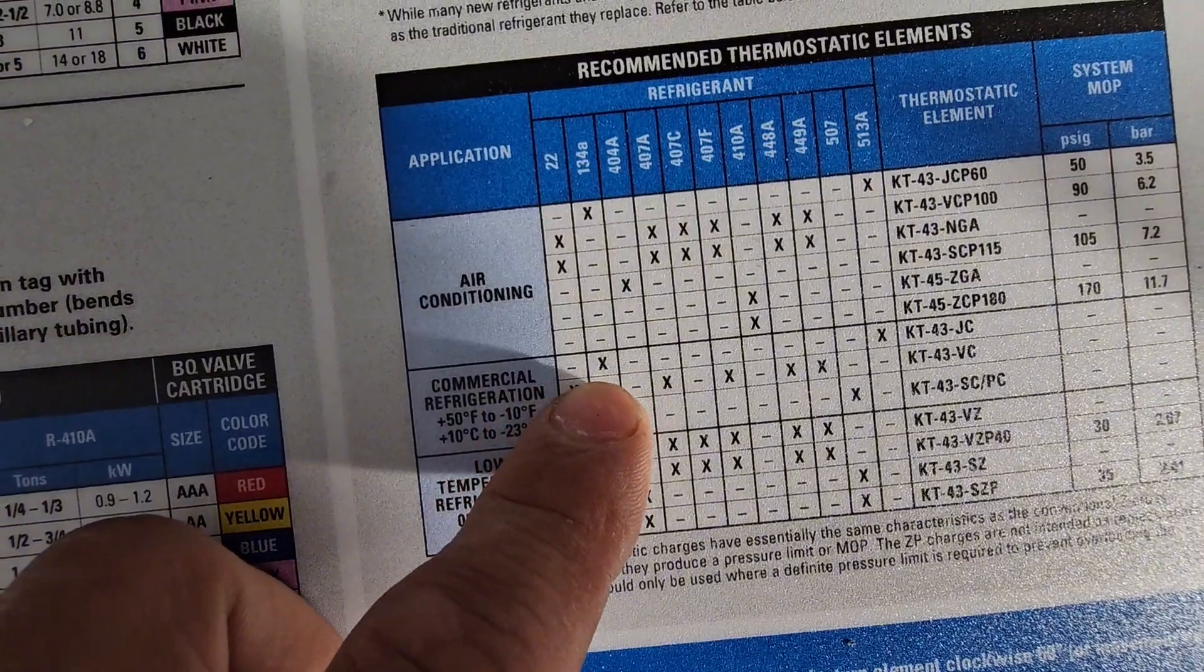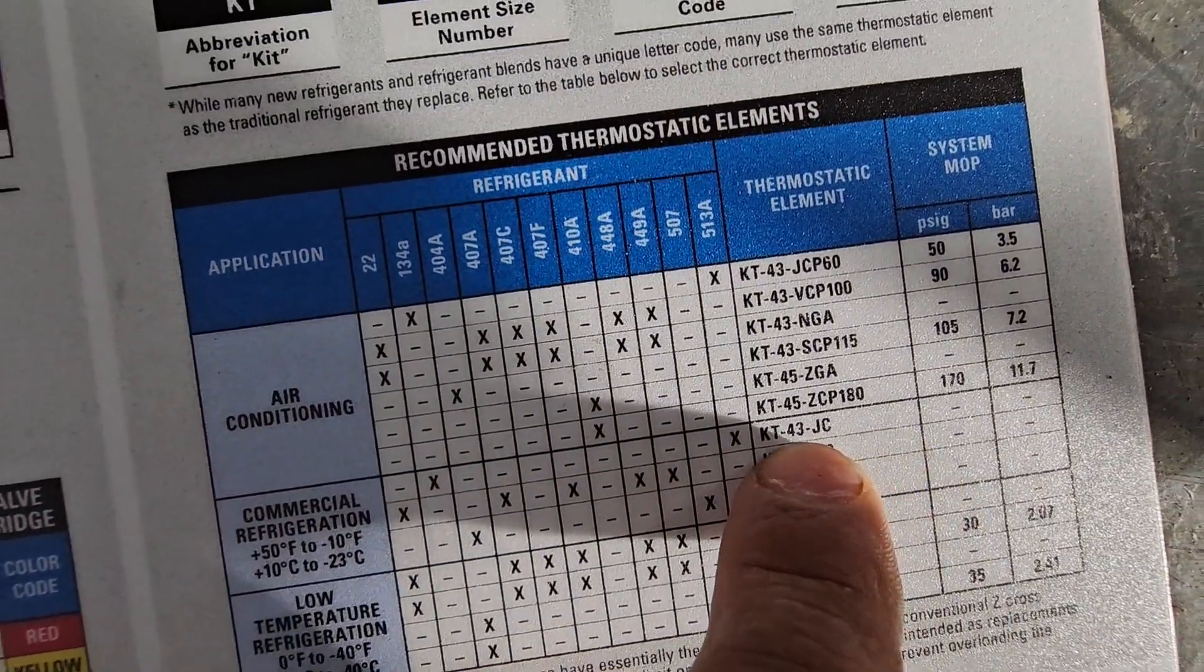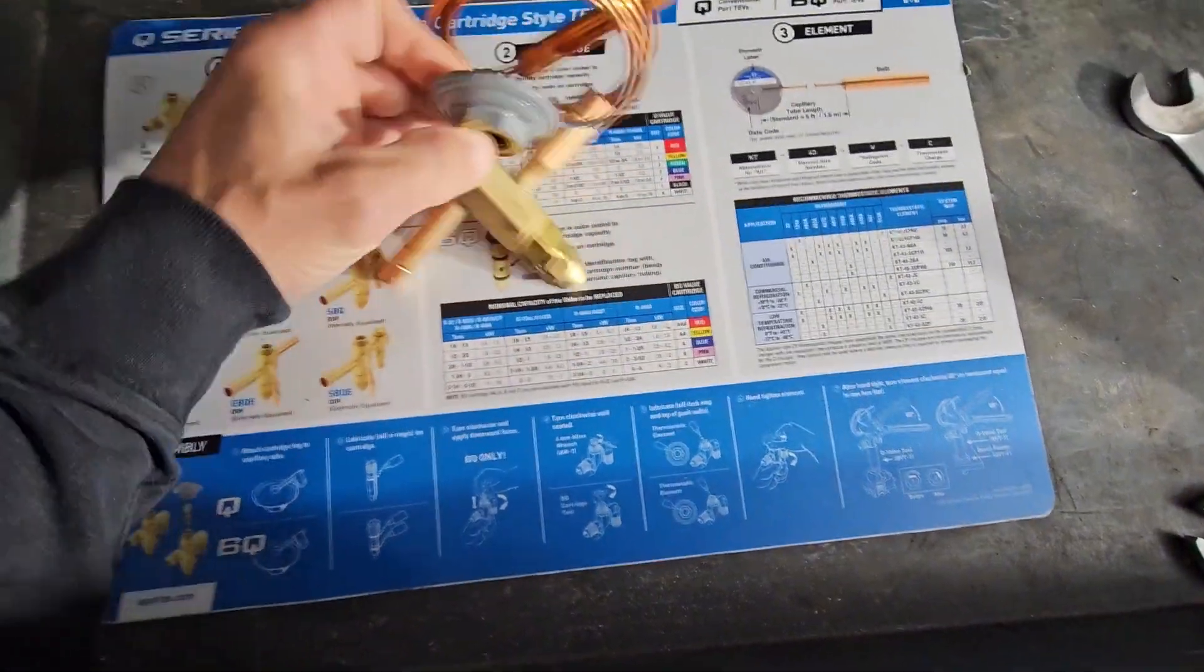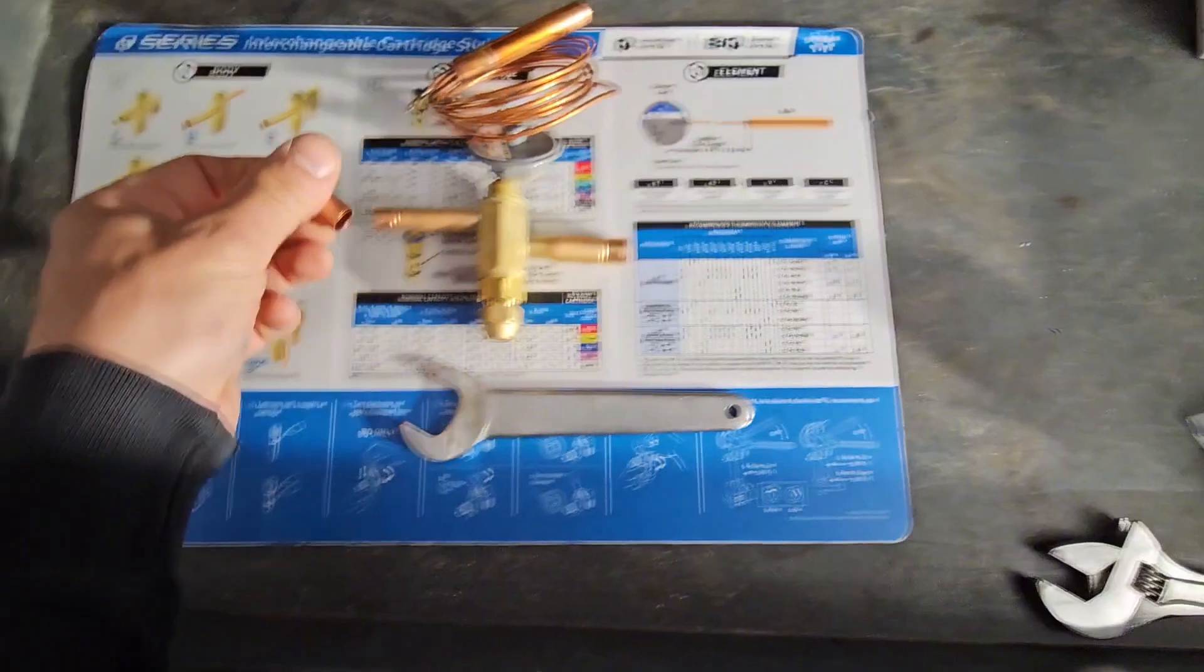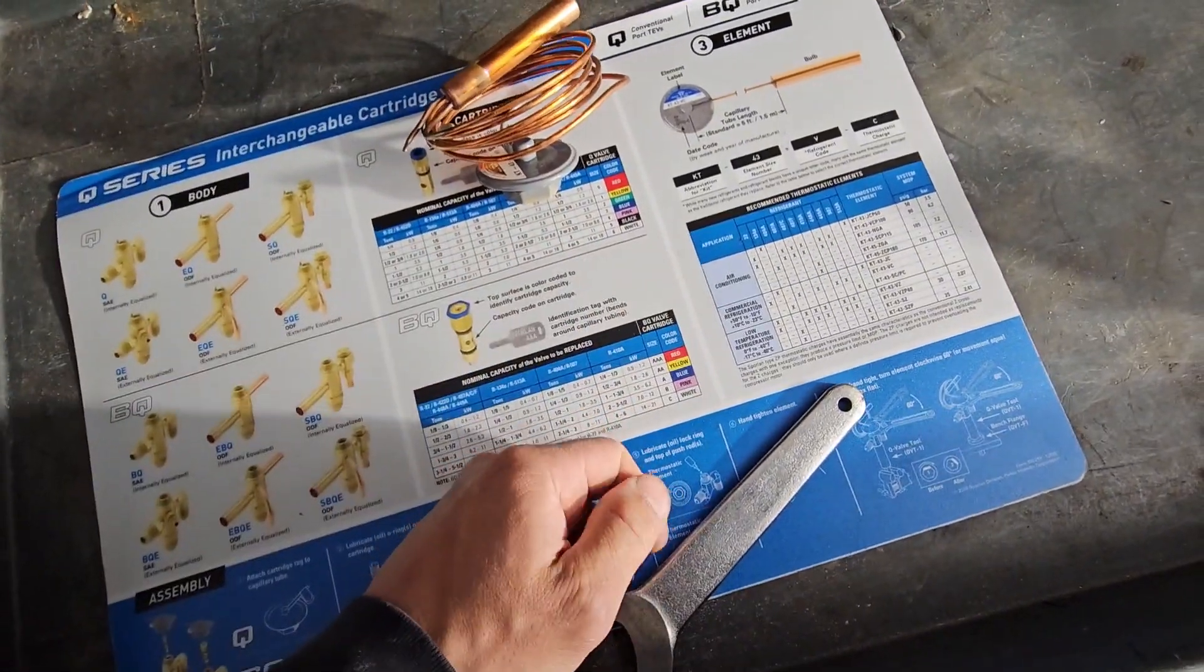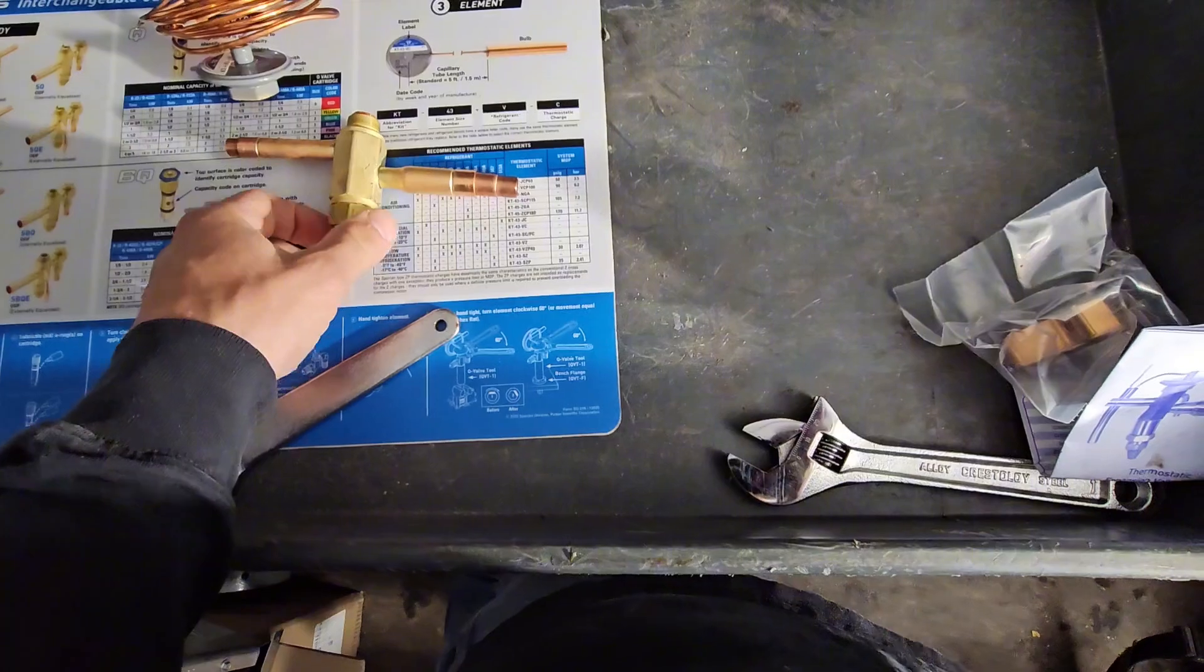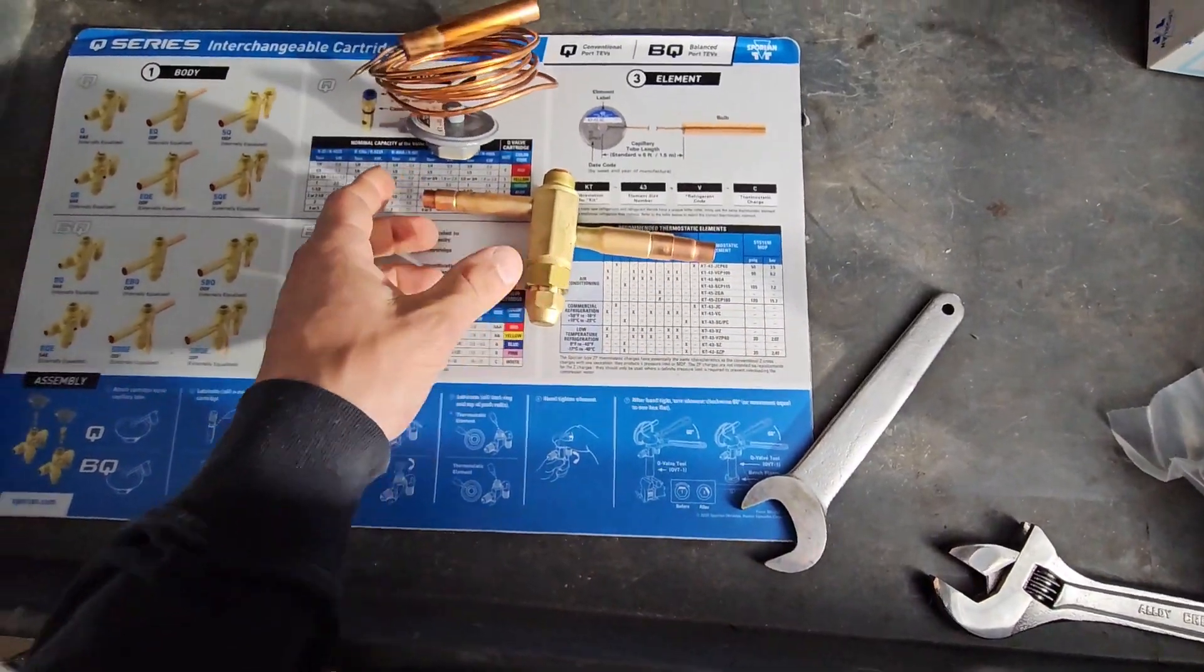So basically we're doing commercial refrigeration and we're using 134a, we want to use a KT43JC, which is what we have here. And that's pretty much it. So I can't screw this on with the camera in my hand, so I'm gonna screw on my power element, I'm going to put my reducer on my outlet, I'm gonna put my reducer on my inlet, and I'm already gonna rough in this valve into this coil.